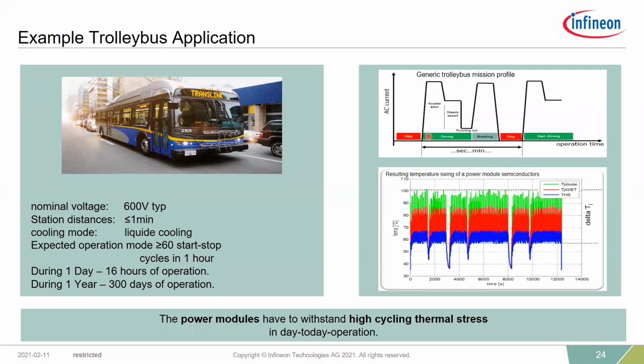As I mentioned, during start-stop operations at a stalled condition, or at a locked rotor condition, you may end up with an initial starting inrush current. Then once the vehicle starts moving and generates inertia, the load on the motor comes down. This is how the profile looks for every start and stop operation. You can see the ripple on the semiconductor side. The green curve represents the temperature ripple of the diode, and the red is the temperature ripple of the IGBT. This is quite important from the semiconductor perspective, since every delta T is a kind of life-killing activity happening at the semiconductor front.